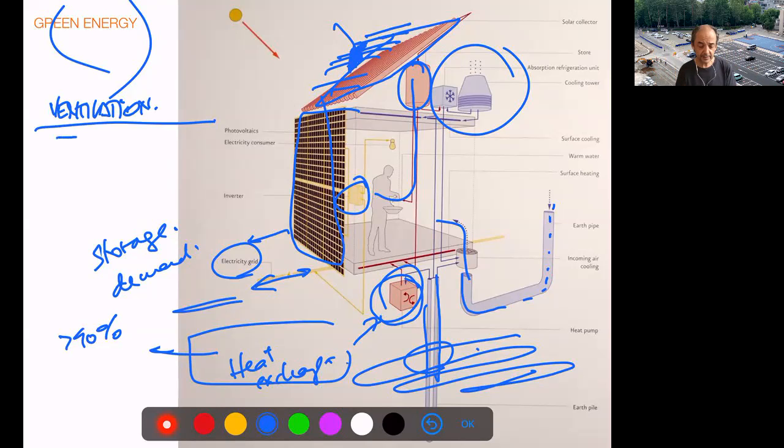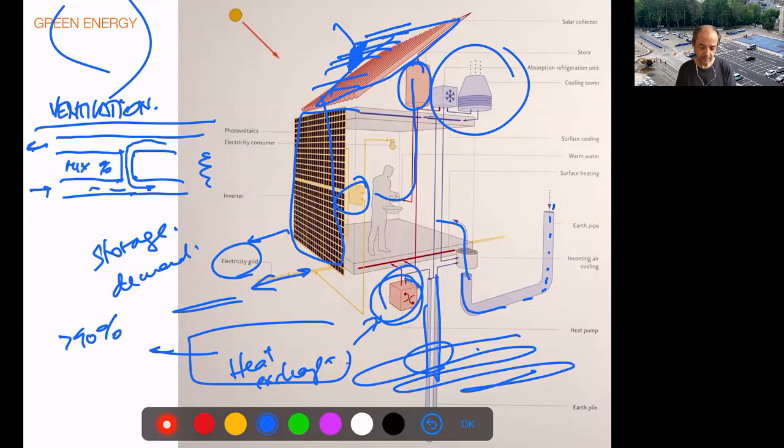And many of them have this kind of exhaust air intake going to the cooling or the fan room. And there is a proportion of the exhaust being mixed, right? And there's a percentage of mix of exhaust and fresh air, which is very traditionally done because that saves energy. So you may mix it 20%, 50%, 60%, and that's an air you reuse.